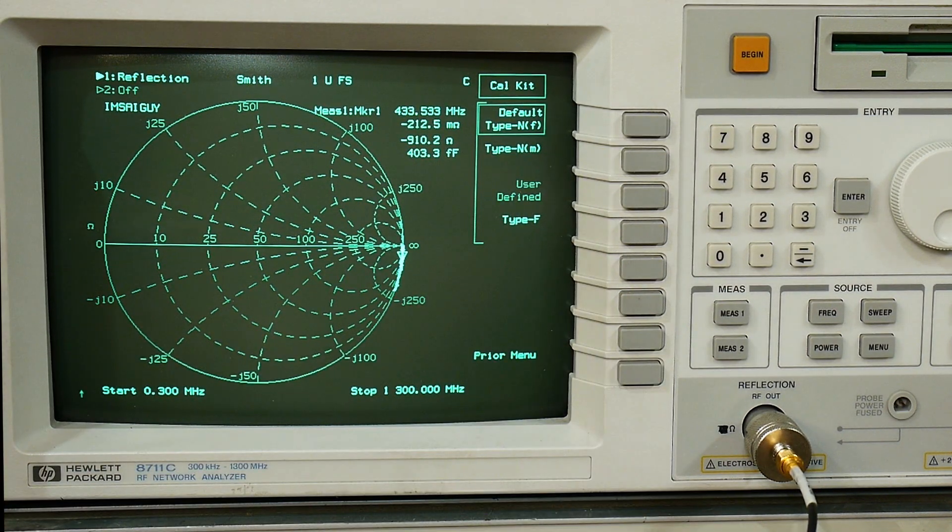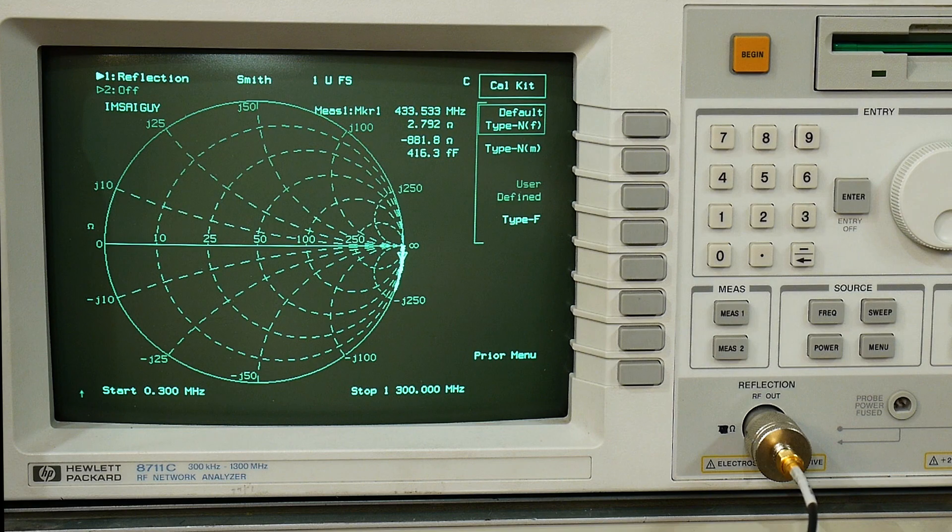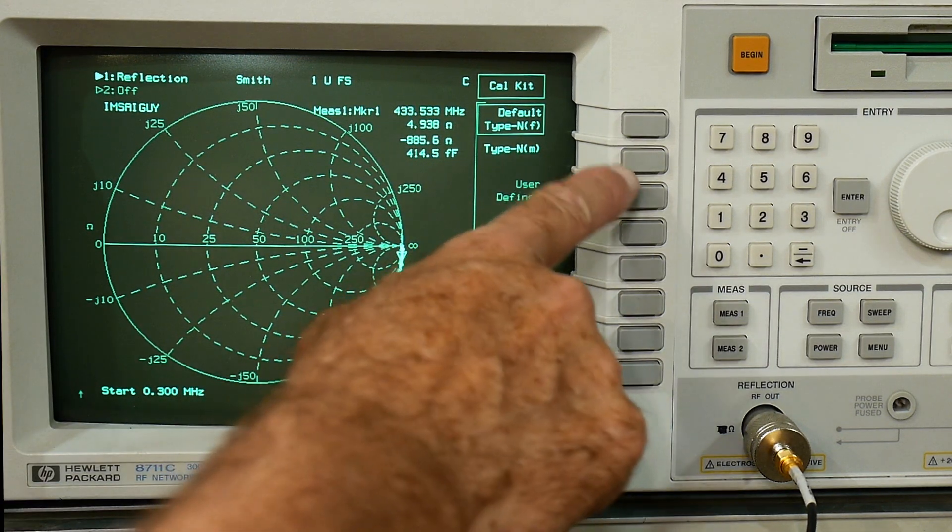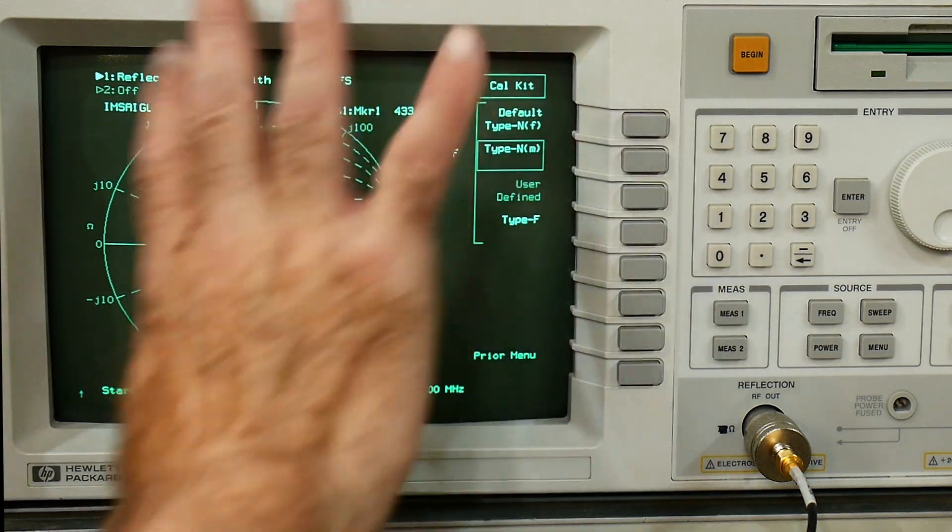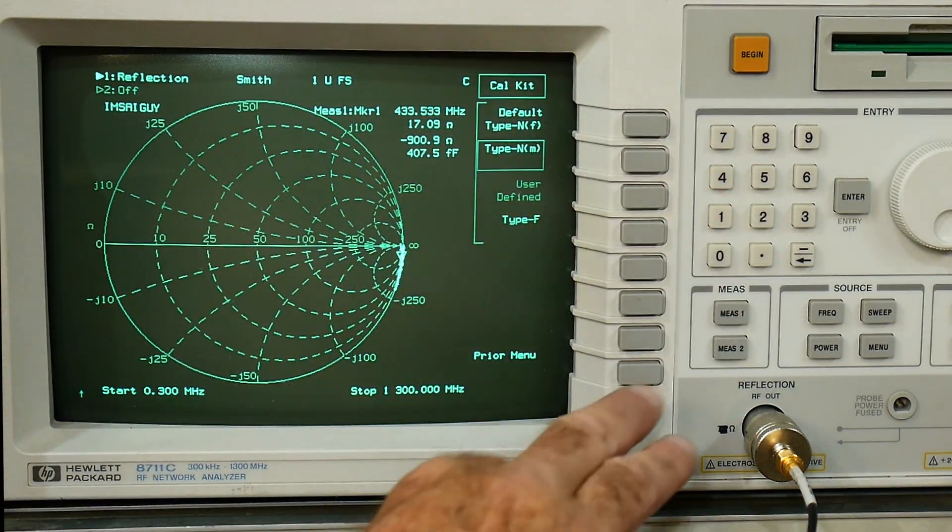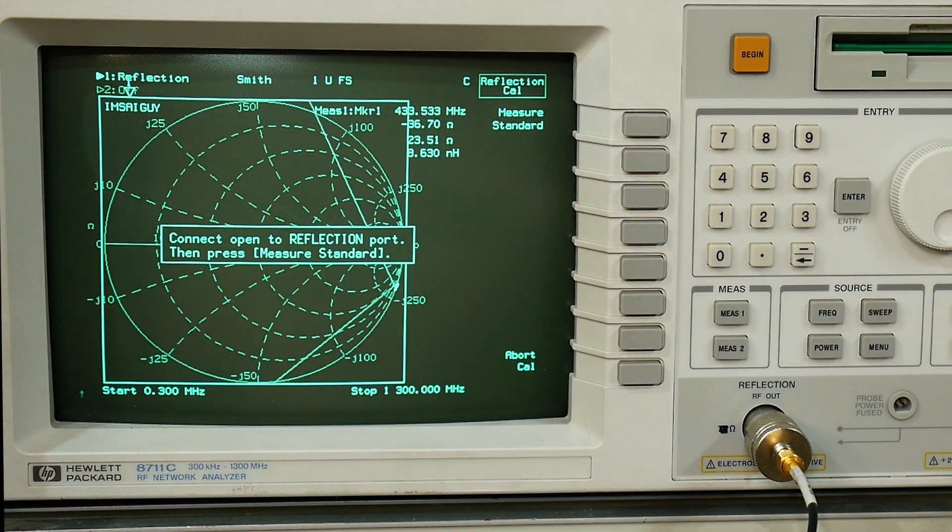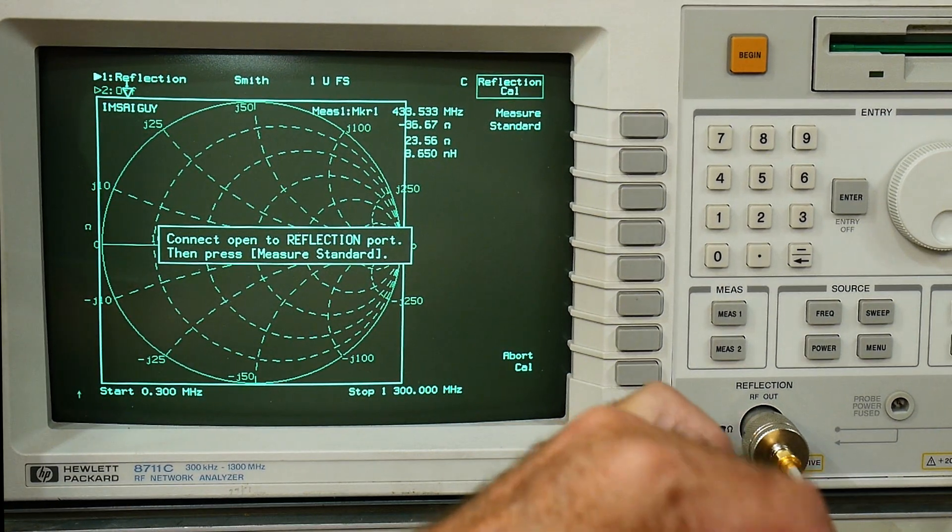I'm here in the calibration menu and you go to cal kit and it says default cal kit. Do not use the default cal kit. Say type N which is just a generic thing. If you go to the generic thing and then go back to calibrate, let's calibrate with the generic thing.